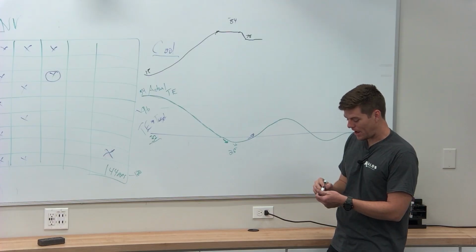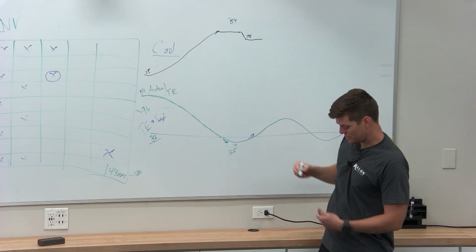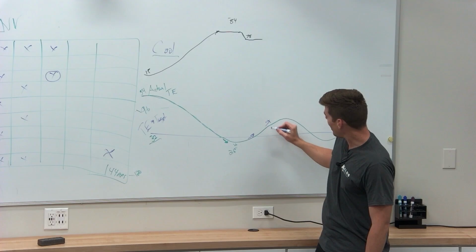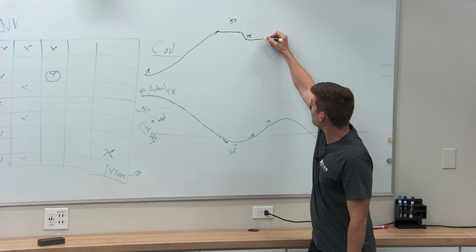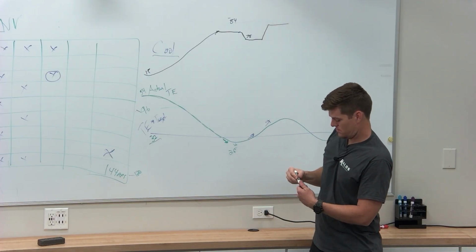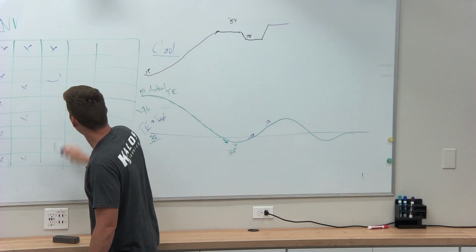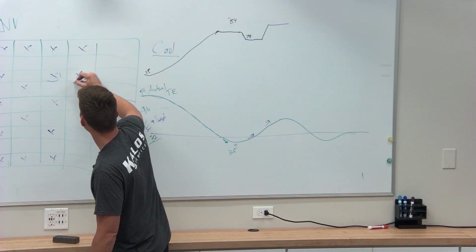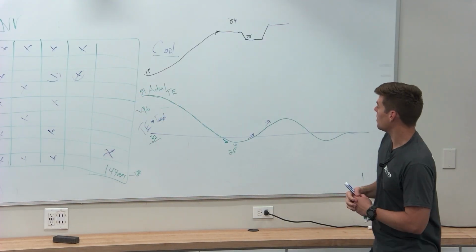So what happens to my actual TE? The pressure goes up. So if the pressure goes up, what goes up too? The saturation temperature. And so it goes up. And so then what does the compressor say? The compressor says, oh crap. So it goes up, right? So it says, oh no, this isn't working. I'm floating. So it says, okay, let's crank this thing up, right? And so it goes up a couple more speeds, higher than what it was before.